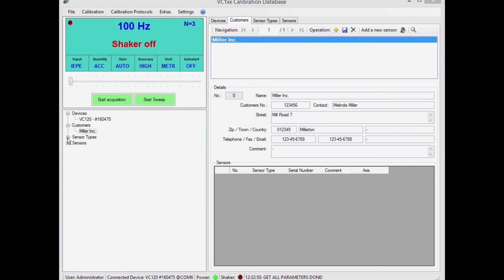Database-supported calibration is by far the more practical of the two options. Calibration is carried out automatically in accordance with saved templates. Results are assigned to customers and stored in the database. The database hierarchy is reflected in the selection tree at the bottom left. Below your VC120, you'll see the selection menu for customers, sensor types and sensors.